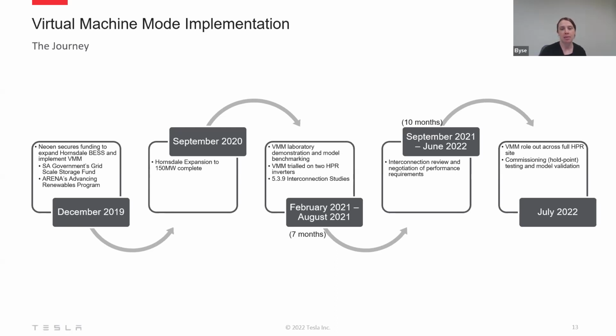Between September 2021 and June 2022, the interconnection studies and package were under review, and the performance requirements of the plant with virtual machine mode on were under negotiation. That was agreed by June 2022, and last month we rolled out the feature across the site, undertook the commissioning or hold point testing and model validation, and now the site is running with grid forming mode switched on. Next slide, please.